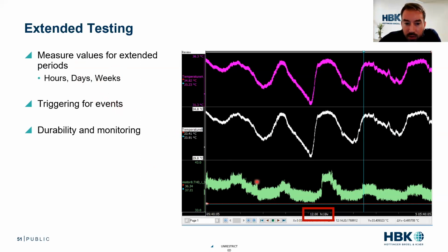Here's an example where we were monitoring temperature and THD on a motor. If you look down here, we have 12 hours per division. I think this was a 5-day test where we were looking at a motor's THD and triggering when it got above certain levels to understand what was happening to this motor over time. So you absolutely can track things like harmonics and temperature for days or weeks if you're really looking for durability type testing.